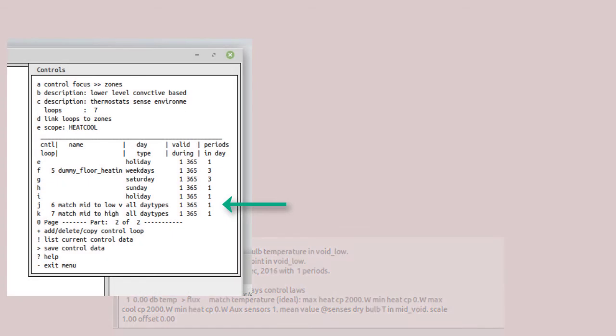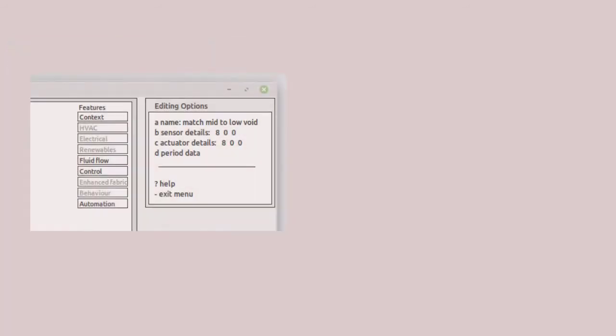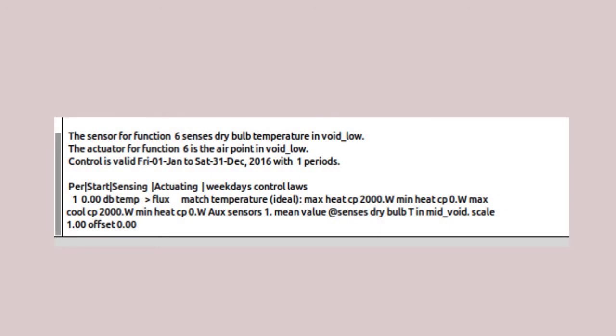In the control definitions, we need control loops for the lower ceiling void and one for the upper ceiling void. They can use a very simple schedule that needs to apply all days at all times. The attributes we need to give it are a heating and cooling capacity to enable the matching, and a pointer to which zone to match.